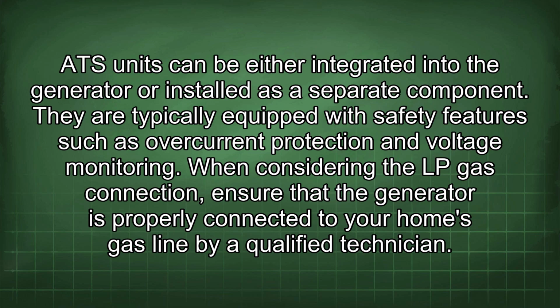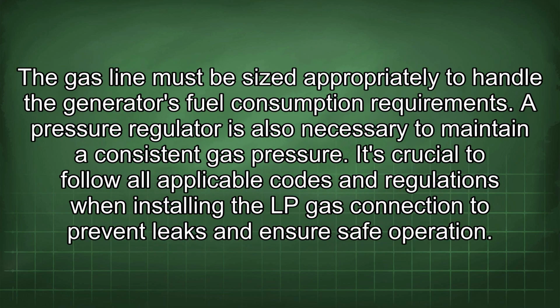When considering the LP gas connection, ensure that the generator is properly connected to your home's gas line by a qualified technician. The gas line must be sized appropriately to handle the generator's fuel consumption requirements, and a pressure regulator is necessary to maintain consistent gas pressure. It is crucial to follow all applicable codes and regulations when installing the LP gas connection to prevent leaks and ensure safe operation.